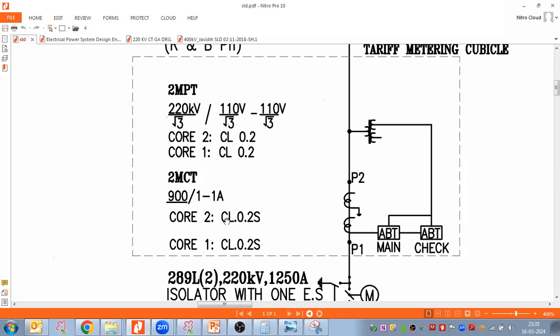If you are using a PX class CT for the metering, say we are using a low knee point voltage, during the fault condition the CT will get saturated. At that time, the metering CT will not read anything, right? And that saturation is desirable, low knee point voltage for metering. Yes, they take a low saturation level. In that case, I think the meter will read the fault current also. Then the fault maximum demand will also get changed.